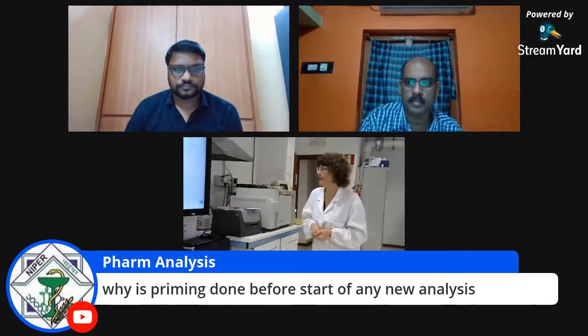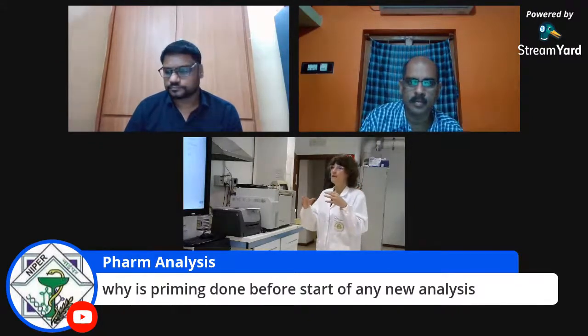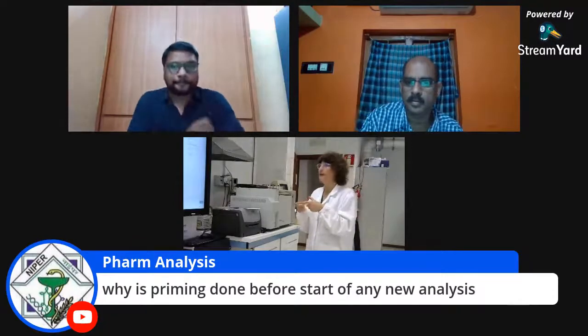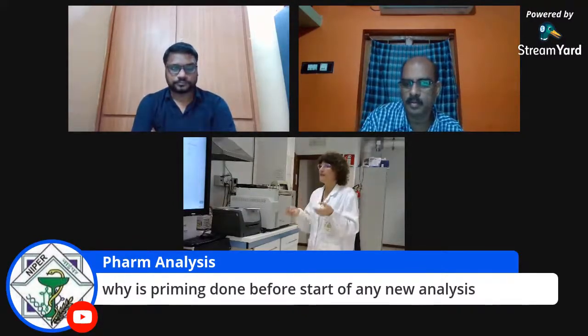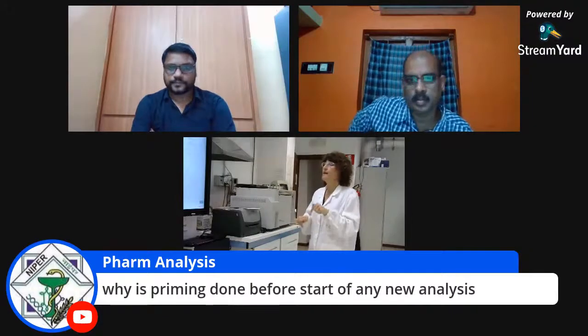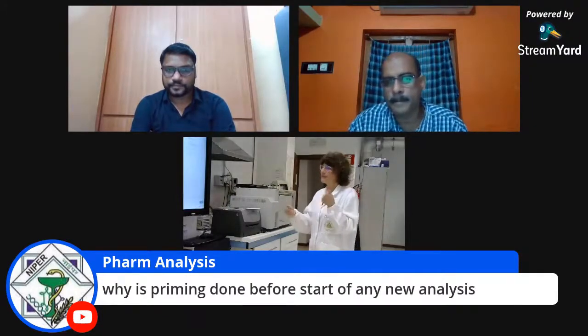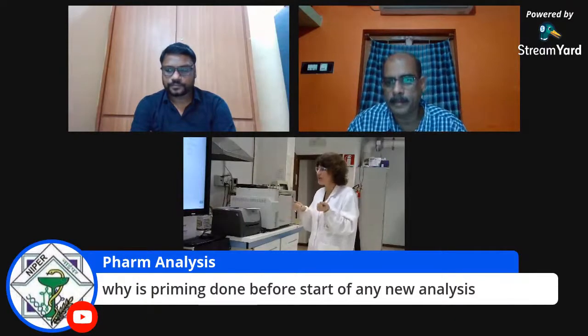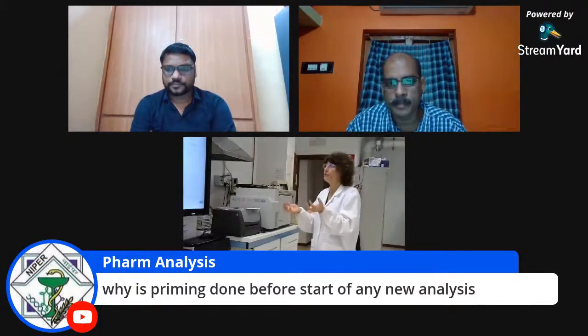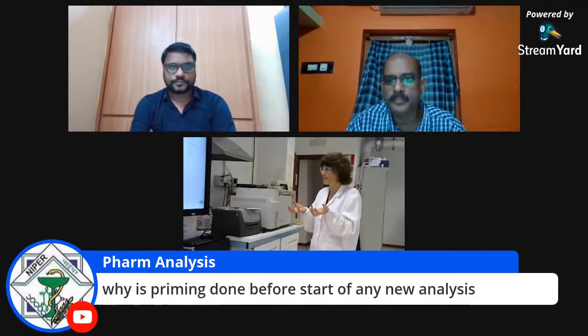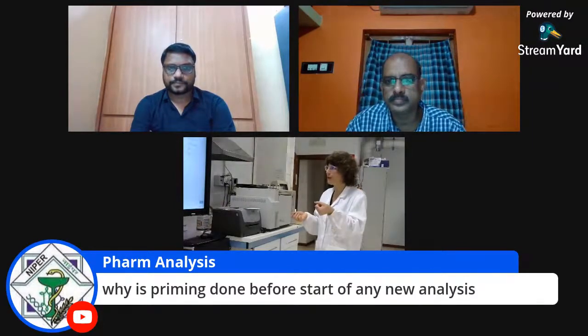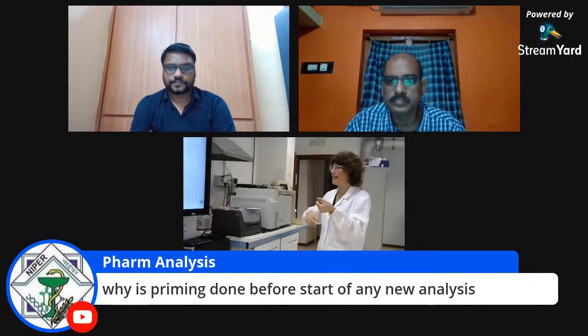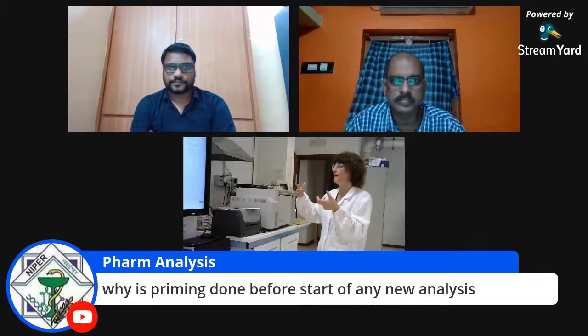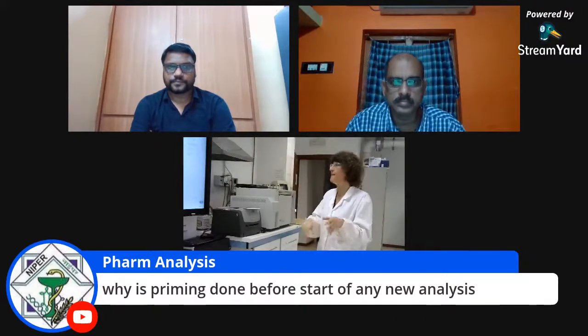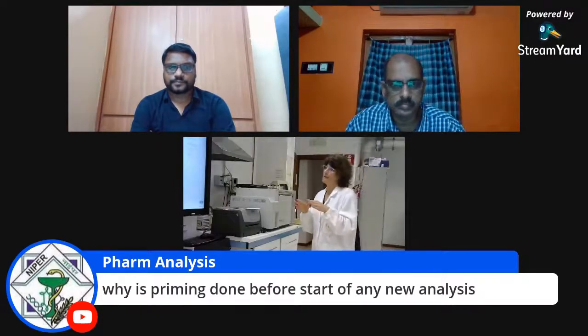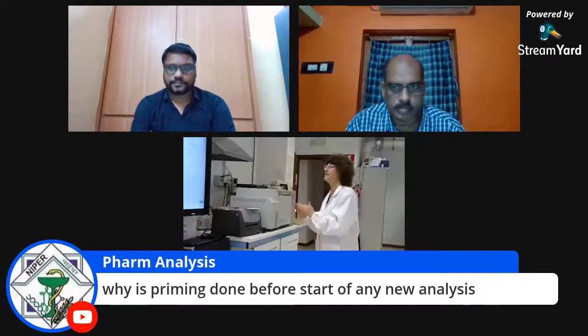Priming time before the start of a new analysis. Yes, because usually some big bubbles build up in the system. If this is the case, the degasser would not be enough to eliminate the very big bubbles. For this reason, with the purge valve open, you wash the system and the very big bubbles go to the waste, and then, with the system washed this way, you can start the analysis.